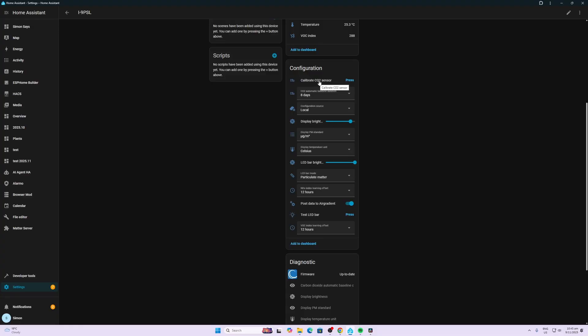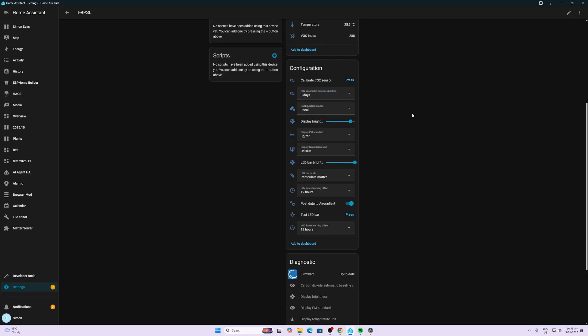We can calibrate the CO2 sensor by placing the device outdoors, pressing this button and then we'll record a baseline for CO2 measurement to make it more accurate. We can also adjust the number of days for the automatic baseline duration. We can configure whether we want local or cloud connection.